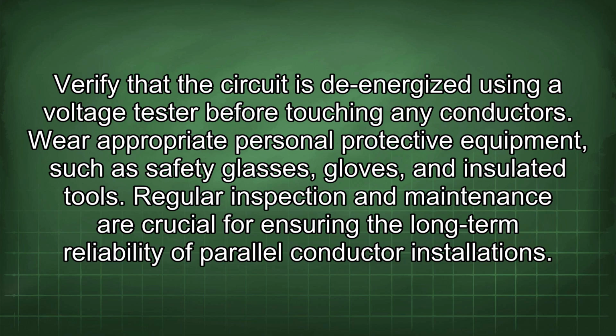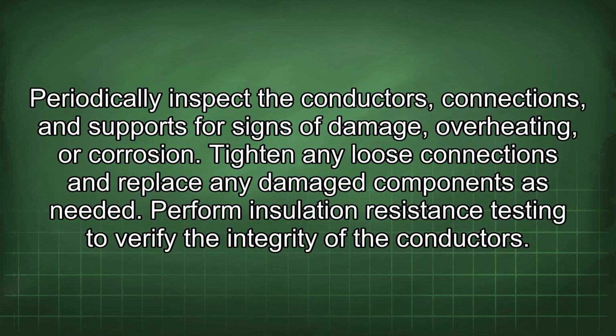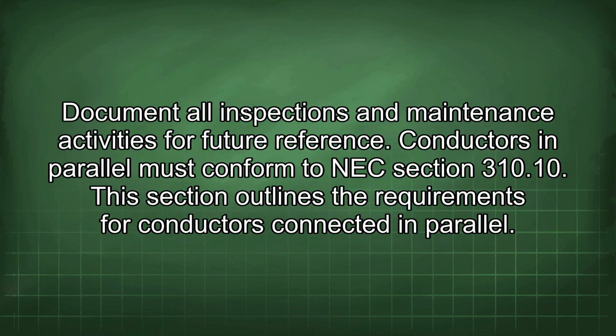Regular inspection and maintenance are crucial for ensuring the long-term reliability of parallel conductor installations. Periodically inspect the conductors, connections, and supports for signs of damage, overheating, or corrosion. Tighten any loose connections and replace any damaged components as needed. Perform insulation resistance testing to verify the integrity of the conductors. Document all inspections and maintenance activities for future reference.